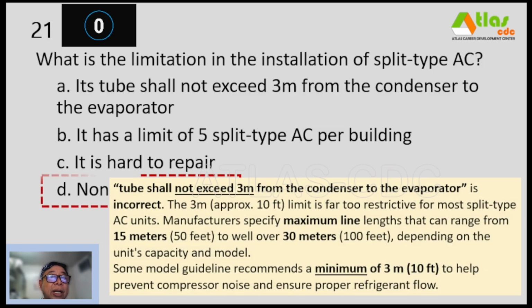And our correct answer is none of the above. So for letter A, the tube shall not exceed 3 meters from the condenser to the evaporator is incorrect also. The 3 meters, approximately 10 feet limit is far too restrictive for most split-type AC units. Manufacturers specify maximum line lengths that can range from 15 meters, 50 feet, to well over 30 meters, 100 feet, depending on the unit's capacity and model. Some model guideline recommends a minimum of 3 meters, 10 feet, to help prevent compressor noise and ensure proper refrigerant flow. So hindi maximum 3 meters, kundi minimum of 3 meters actually ang split type na AC.